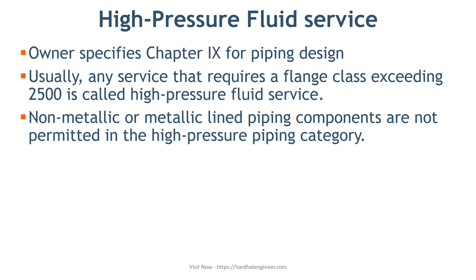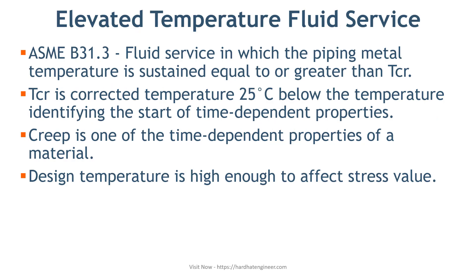The fourth fluid service type is elevated temperature fluid service. ASME B31.3 says that a fluid service in which the piping metal temperature is sustained equal to or greater than TCR — the corrected temperature 25 degrees centigrade below the temperature that identifies the start of time-dependent properties — is considered elevated temperature. Creep is one of the time-dependent properties of the material. That means when your design temperature is high enough to affect stress values, it is considered an elevated temperature fluid service, and you must consider this mechanical property for safe design.